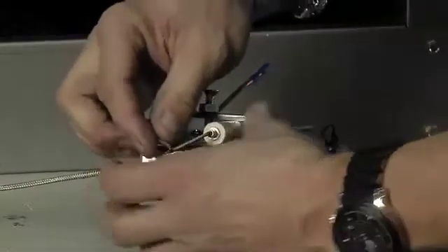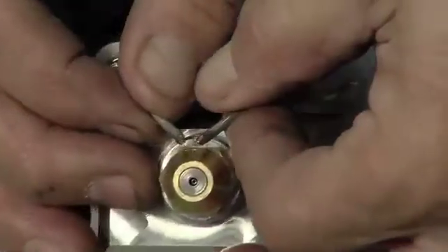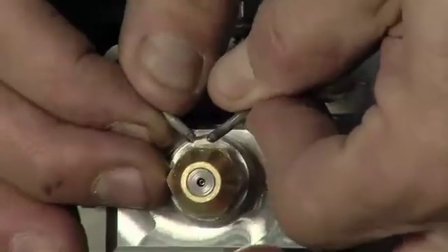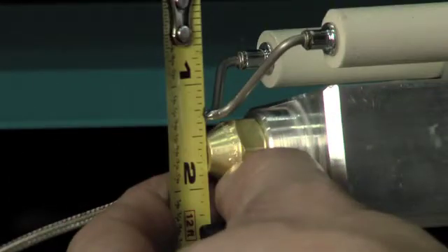The tips of the electrodes are to be flush with the end of the nozzle. The height from the center of the orifice of the nozzle to the tips of the electrodes is to be set at 3 eighths inches.